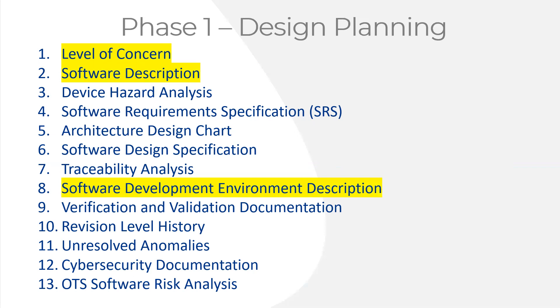The first phase of design is planning. The three documents you should prepare during the planning phase are the level of concern document, the software description, and the software development environment description. That last one is essentially your procedure for how you're going to accomplish software development, document it, and fulfill design controls — if you're combining both into one integrated procedure.